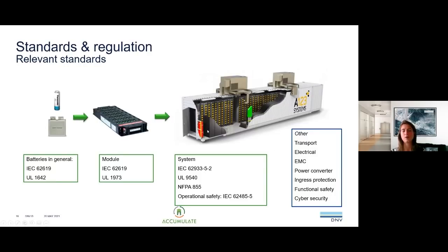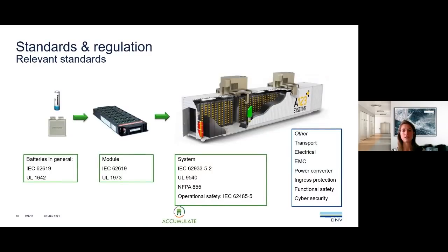When focusing on the system level, the US has a lot of experience and development already in NFPA 855, which has already been discussed today, and UL 9540. The 9540A is the test to check what happens as it fails, to provide input for designing your system correctly, and UL 9540 covers the safety of the whole system.